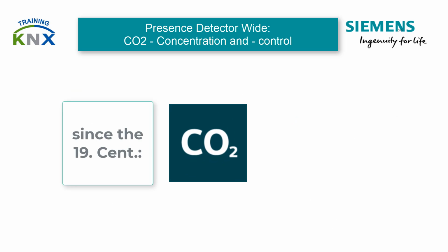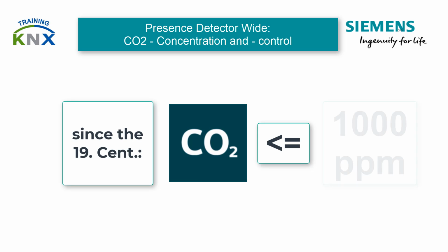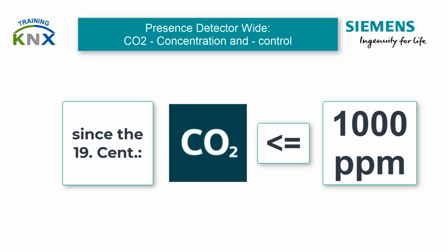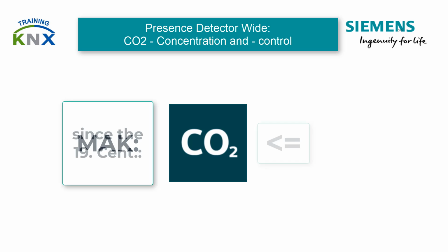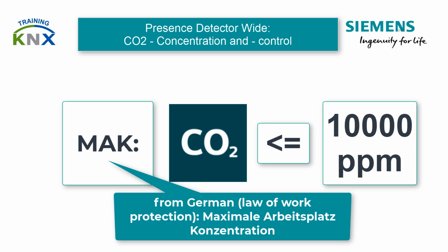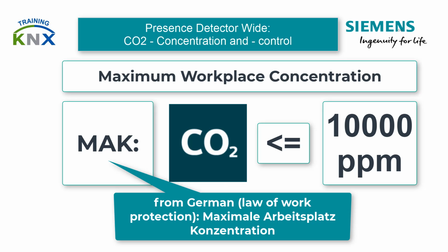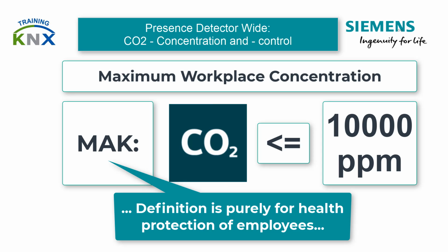Since the 19th century, experts have been demanding that the CO2 concentration in such rooms should not exceed 1000 ppm in the long term. Unfortunately, in contrast to the still valid limit values for the so-called MAK values. MAK stands for Maximum Workplace Concentration.